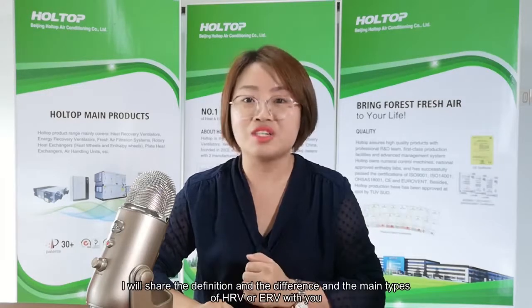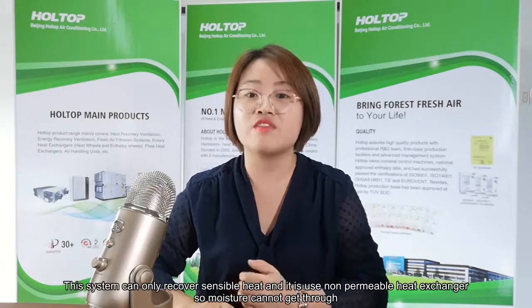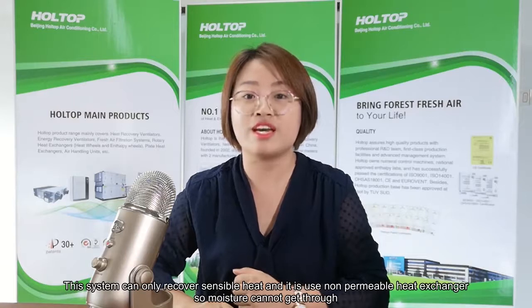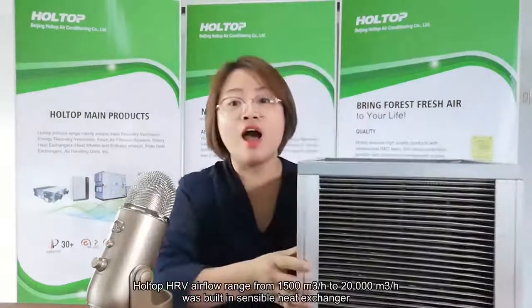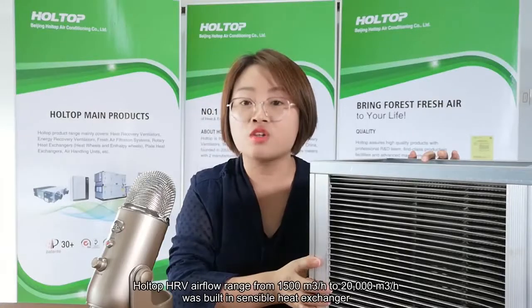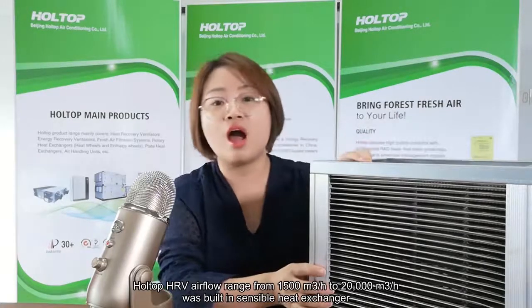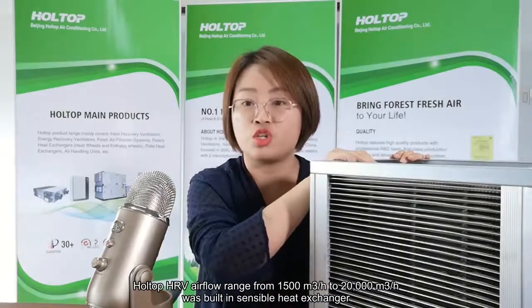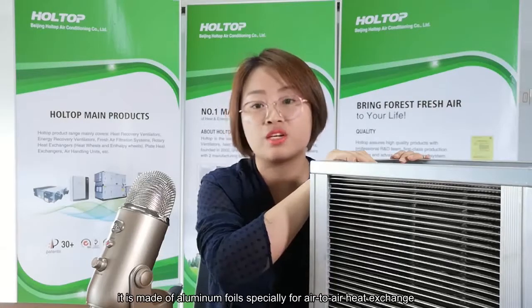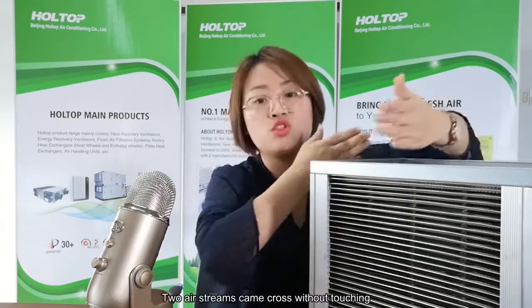So, in this video, I will share the definition, the difference, and the main types of HRV or ERV with you. So, basically, what is HRV or ERV? HRV stands for Heat Recovery Ventilator. This system can only recover sensible heat, and it uses a non-permeable heat exchanger, so the moisture cannot get through. For example, Holtop HRV, with airflow ranging from 1500 to 20,000 cubic meters per hour, is built with this kind of sensible heat exchanger. It is made of aluminum foils, especially for air-to-air heat exchange. The two air streams cross without touching, and various types are available for different applications.